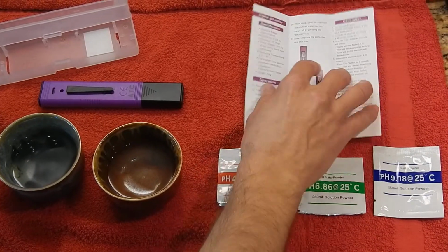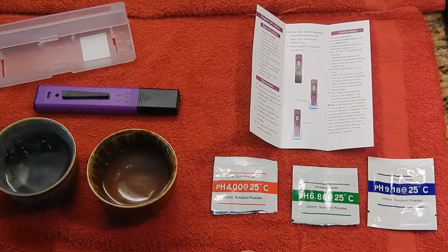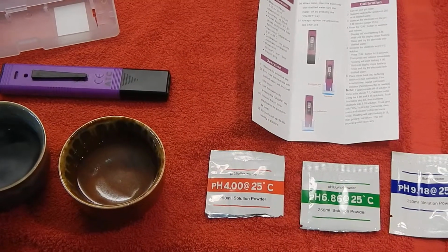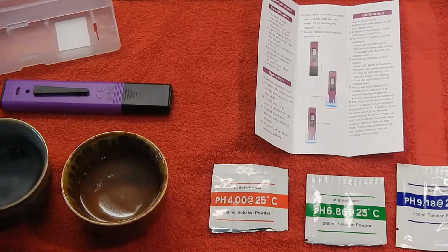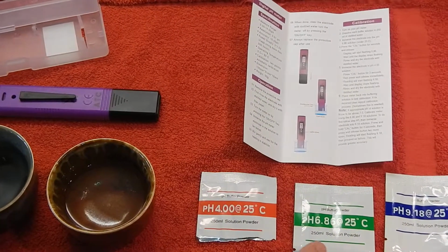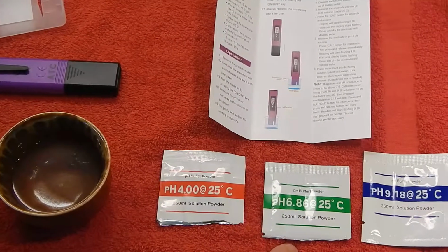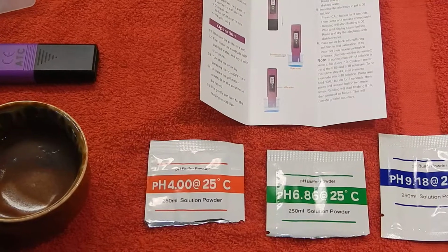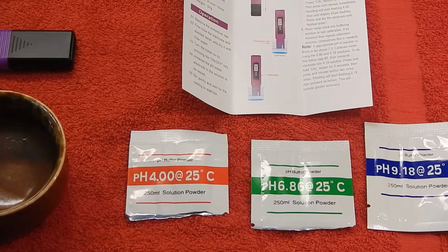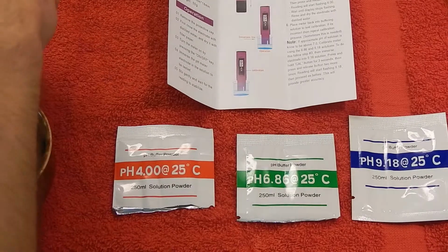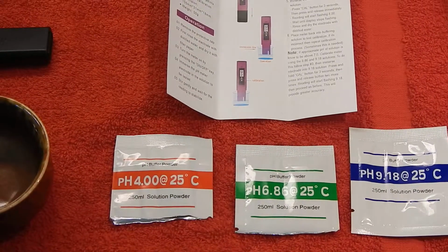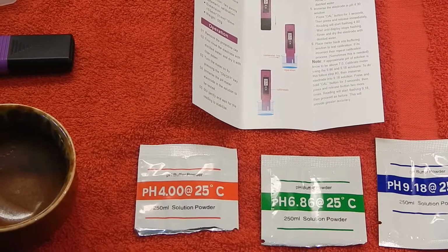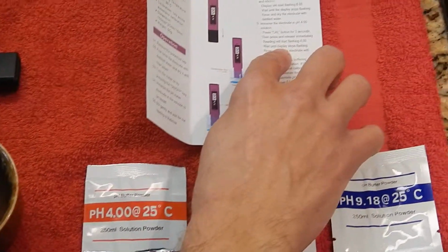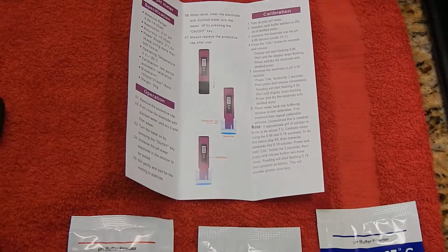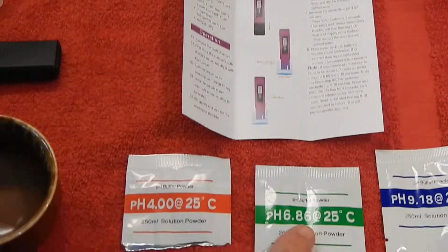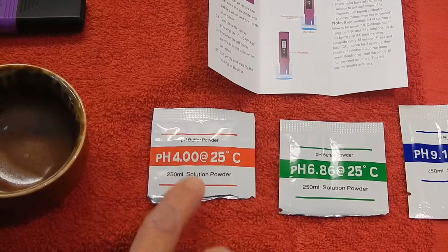And to calibrate, you just go ahead and follow the instructions that are detailed here in the user guide that comes with the device. But basically, you just clean the electrode, blot it dry, you immerse it into the 6.86 buffer solution. Do just like I did before. You gently stir it and hold the on button for about a couple seconds. It'll start blinking, and after it's blinking for a little while, as it shows here, the reading starts flashing. You wait until the display stops flashing, you rinse and dry it, and then after you do the 6.86, you repeat the procedure with the pH 4.